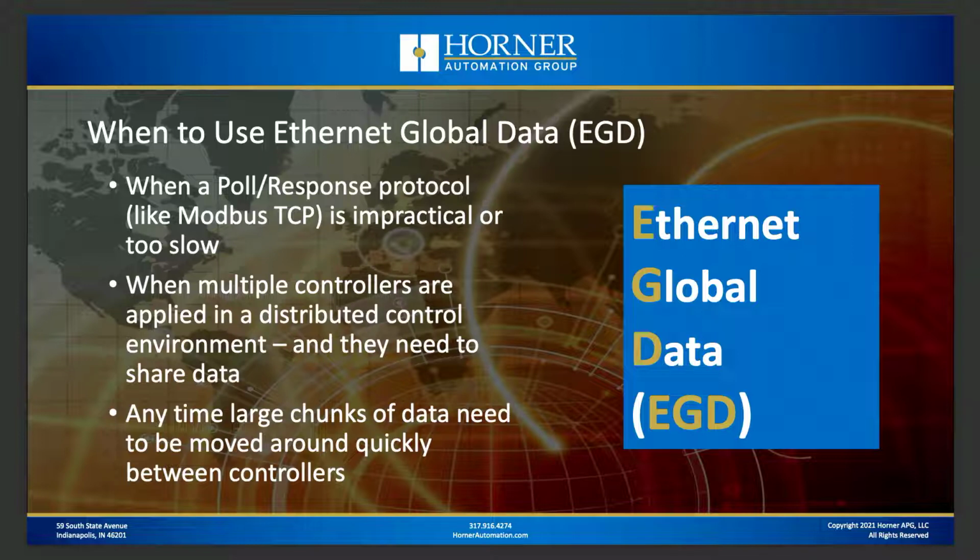Well, with Modbus TCP, that client is going to be polling one after the other the 30 other devices in order to exchange data. That's going to take quite a bit of time, maybe several seconds. So in some scenarios, especially if you're talking about controller communications, that's just too slow.